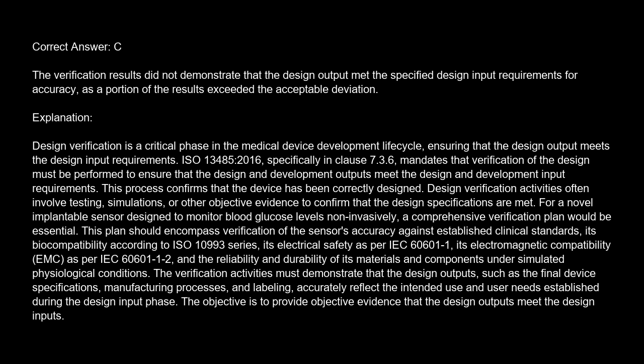design input requirements. ISO 13485-2016, specifically in Clause 7.3.6, mandates that verification of the design must be performed to ensure that the design and development outputs meet the design and development input requirements. This process confirms that the device has been correctly designed. Design verification activities often involve testing, simulations, or other objective evidence to confirm that the design specifications are met.